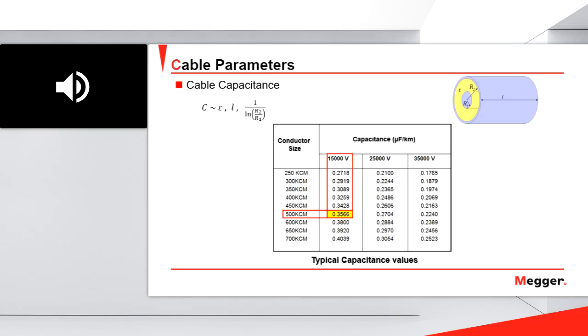Regarding the important cable parameters for fault location, the first one I would like to mention is the cable capacitance. As you see, the cable is a cylindrical capacitor, and the capacitance of my cable will depend on the type of insulation, the thickness of the insulation and the length of my cable. So, for instance, if I have a 15 kV cable with a conductor size of 500 kcmil, the capacitance of my cable in 1 kilometer will be 0.3566 microfarads. If I have 2 kilometers of this cable, I will have double the capacitance.